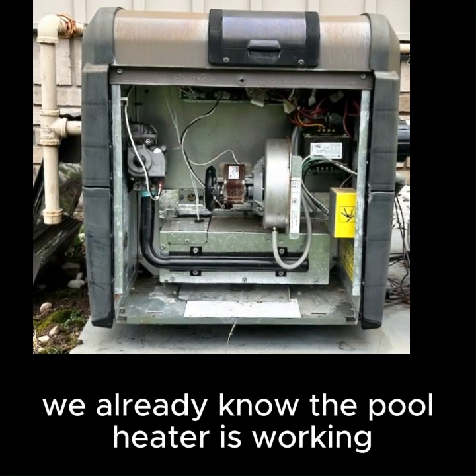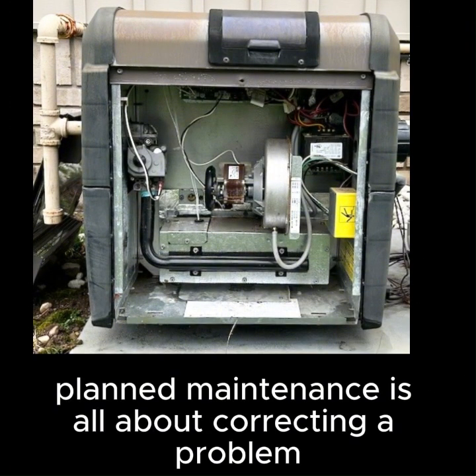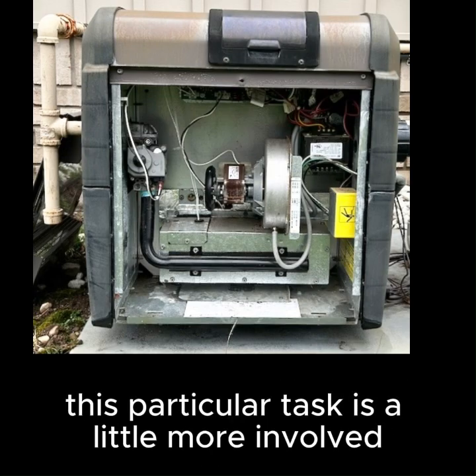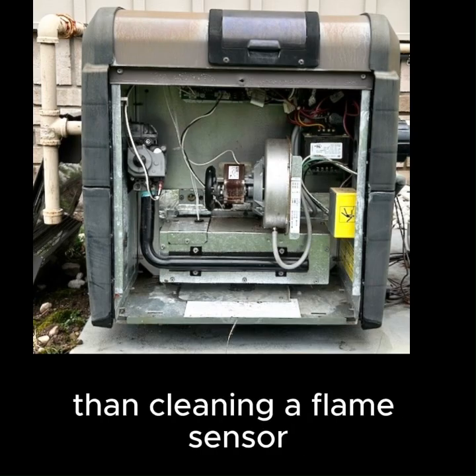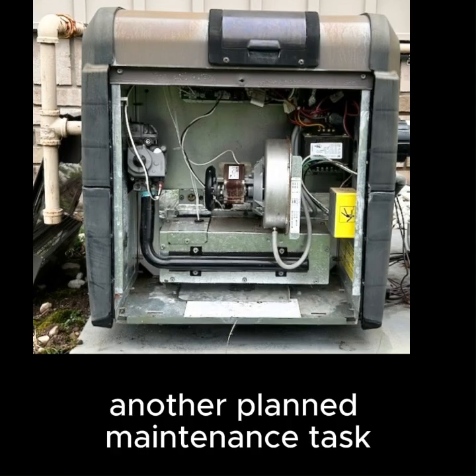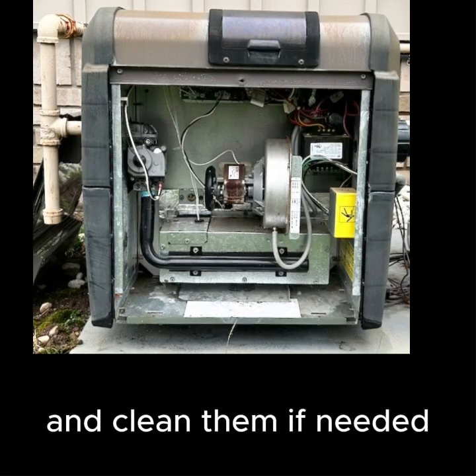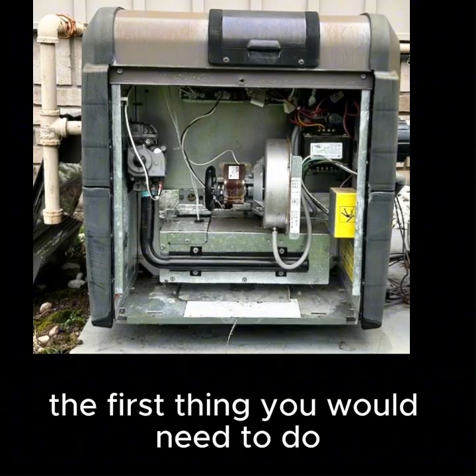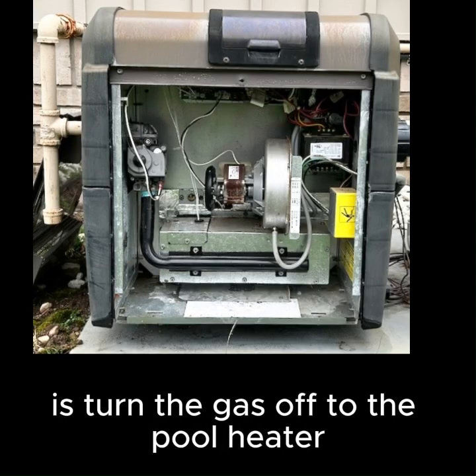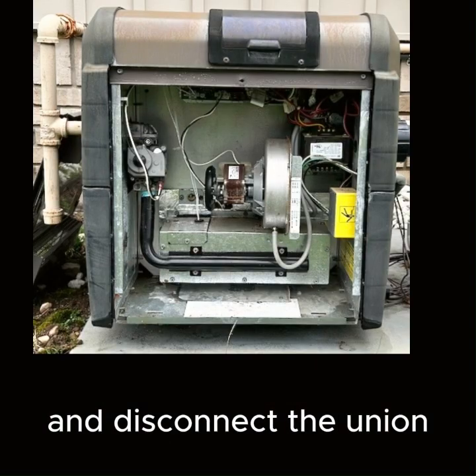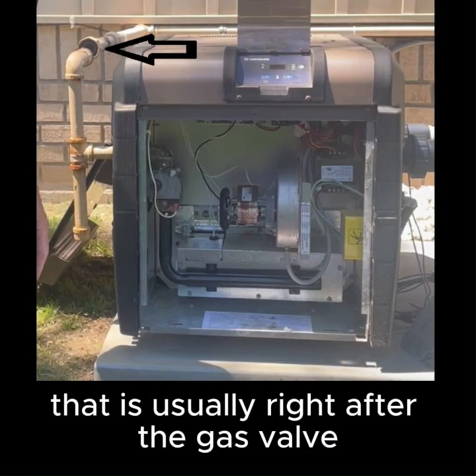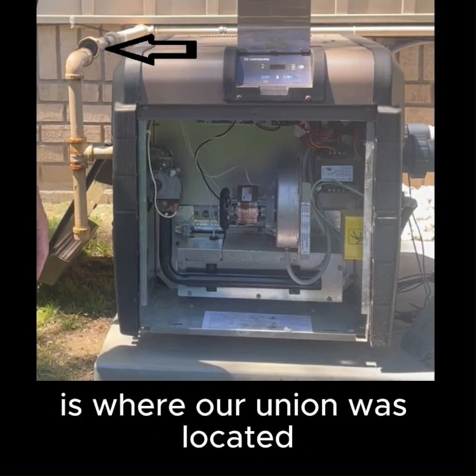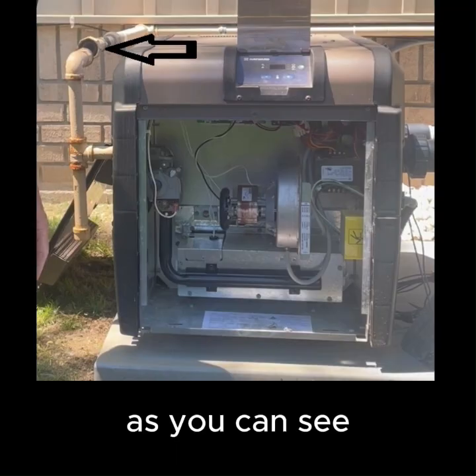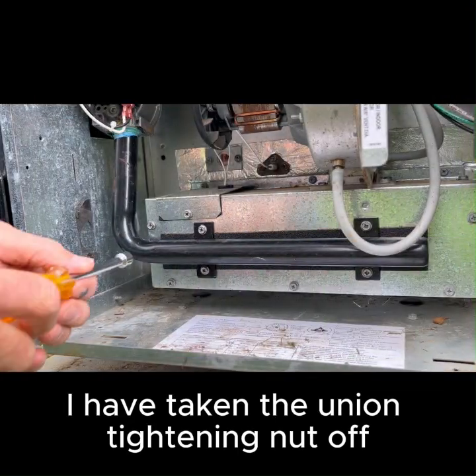Again, we already know the pool heater is working. Planned maintenance is all about correcting a problem before it gets worse. This particular task is a little more involved than cleaning a flame sensor. Another planned maintenance task is to check the burner ports and clean them if needed. The first thing you would need to do is turn the gas off to the pool heater and disconnect the union that is usually right after the gas valve. The picture that I'm showing you is where our union was located. As you can see, I have taken the union tightening nut off.